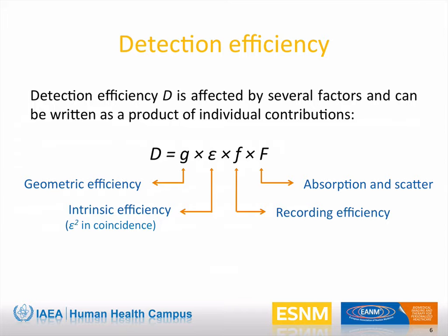However, the minimum scanner diameter is limited by the parallax effect that worsens as scanner radius is reduced. In turn, axial extension is limited, for example, by the cost of the building material. And on the other hand, epsilon can be increased by using thicker scintillating crystals. But, once again, spatial resolution would be degraded by the increased parallax effect.